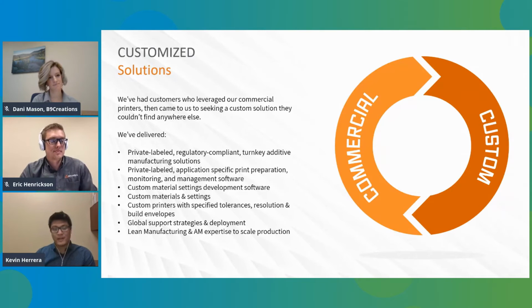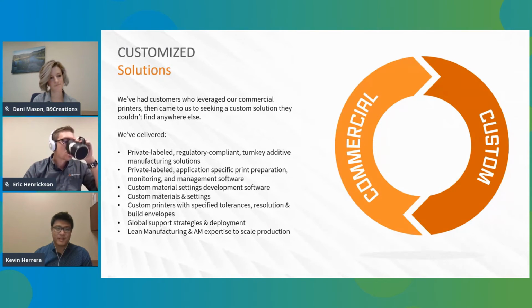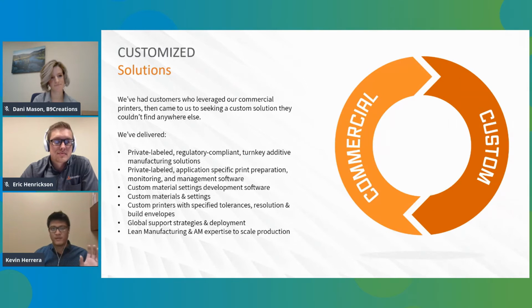I mean, at least in my industry and with catheters, almost everything is plastic. So we work with polymers all the time. The only time we don't have a plastic part on it is when we need the conductive properties or the thermal properties of metal. So like Eric said, it really is application based. But the thing to focus on is that the materials for 3D printing are becoming just as robust as, say, a PEBAX or a PEEK, which is like an off-the-shelf polymer that you can get that are these standards in medical device. And so once these materials start to evolve a little bit more and get a little bit closer, I think you're going to start to see these 3D printed components be used more in human use devices.